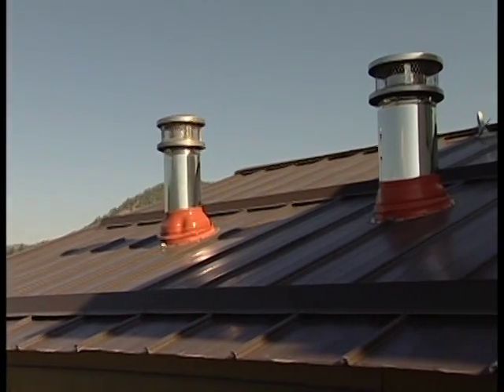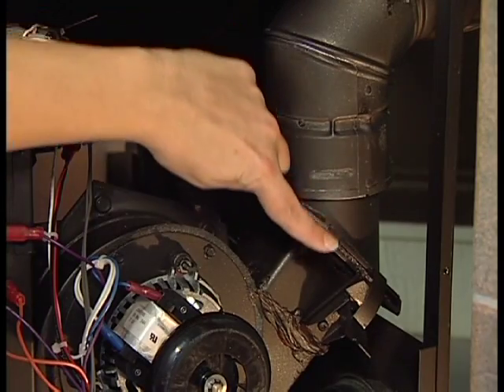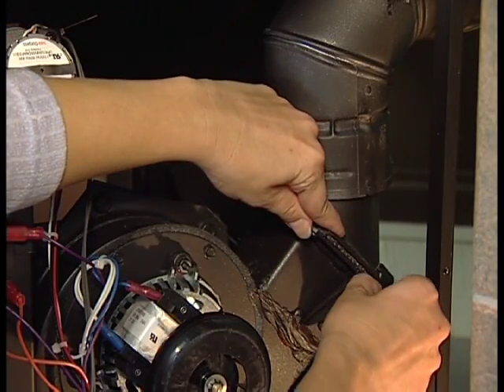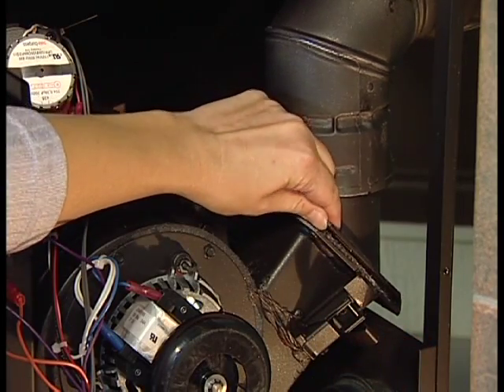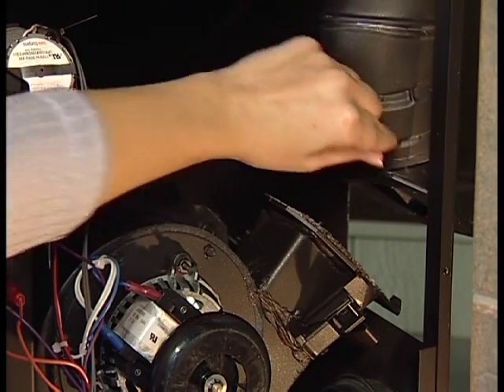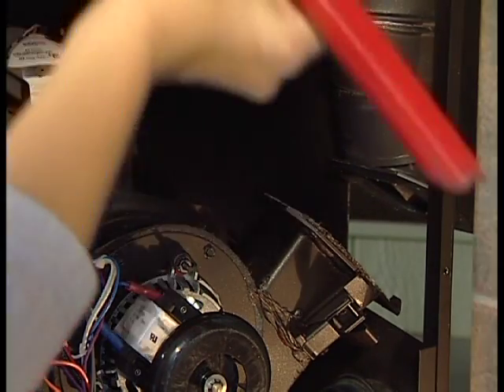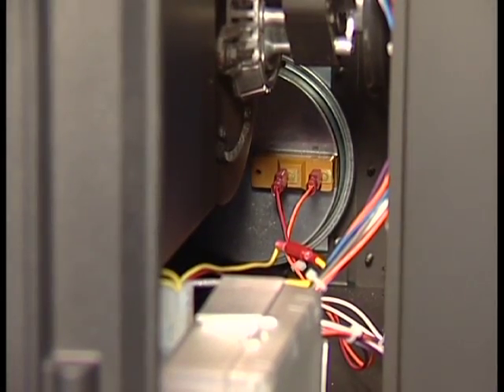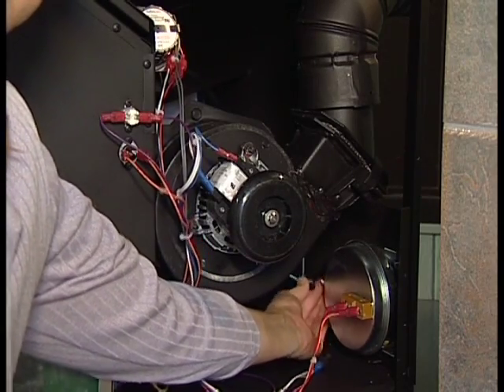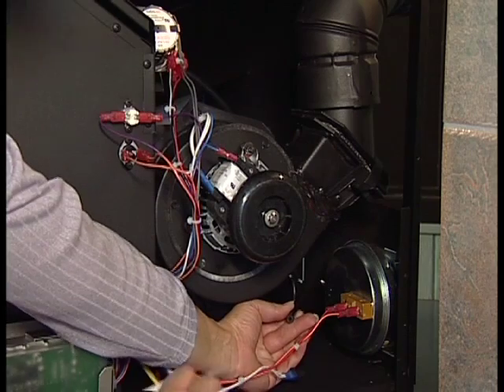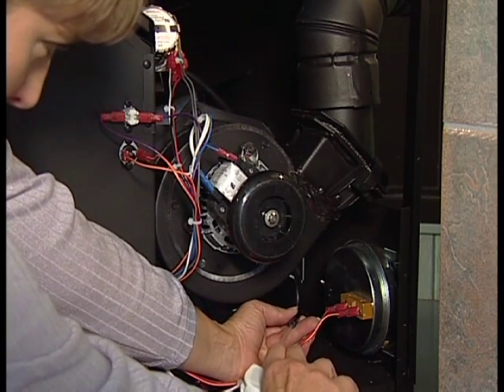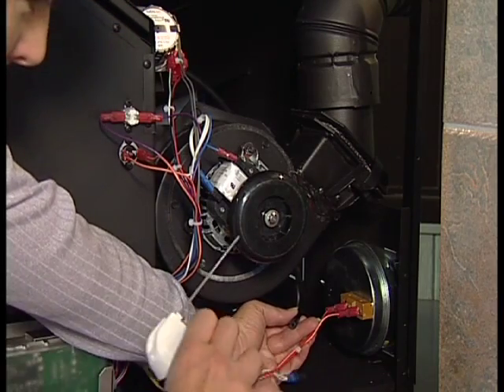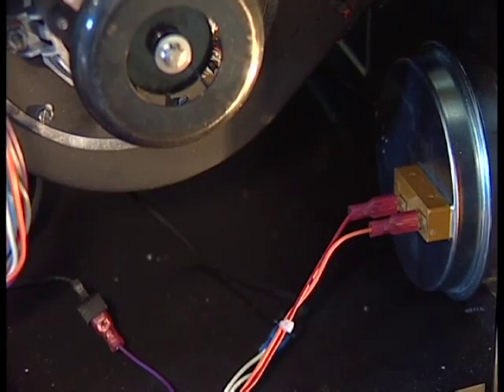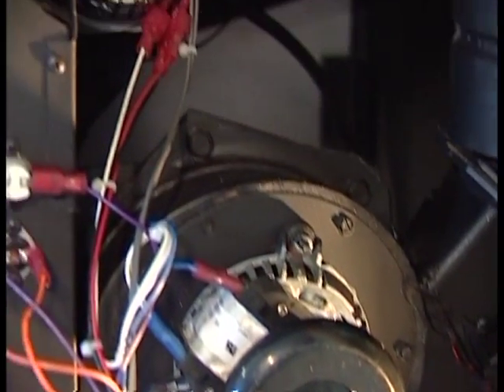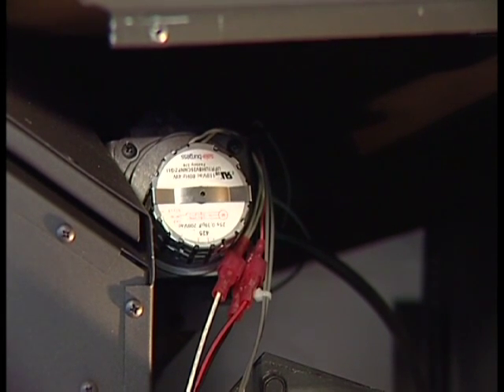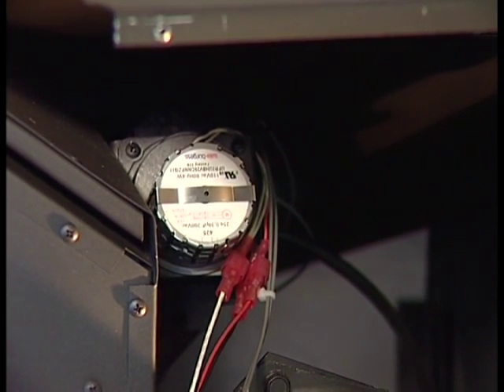Check the vent system. The exhaust blower must come on during the startup cycle and the vent system must be free of obstructions. The vacuum switch will not allow the feed motor to turn on if the exhaust blower does not work or if the chimney pipe is blocked. Check the vacuum switch. Unfasten the end of the supply hose at the vacuum switch and blow compressed air into it to clear it out. Check the feed motor. If the feed motor does not turn, it's possible that the feed auger is jammed or that there is a bad connection in the motor.